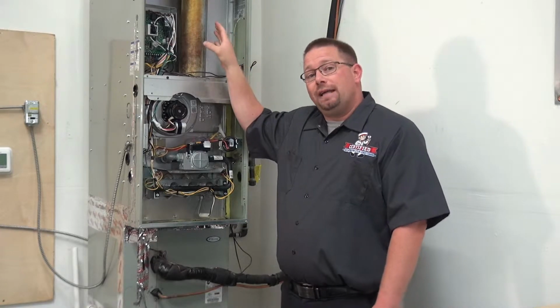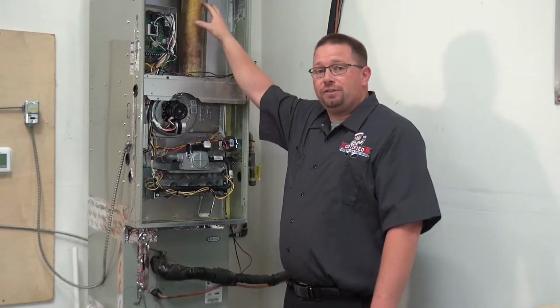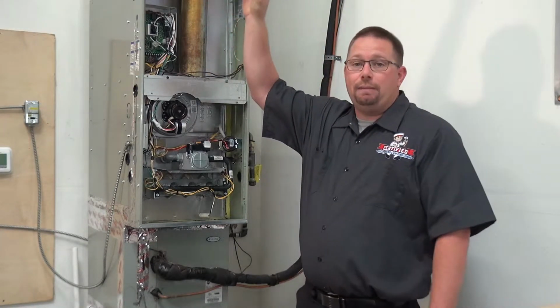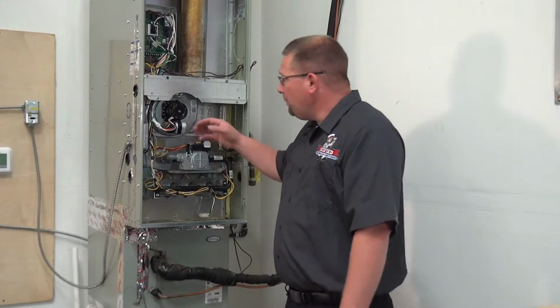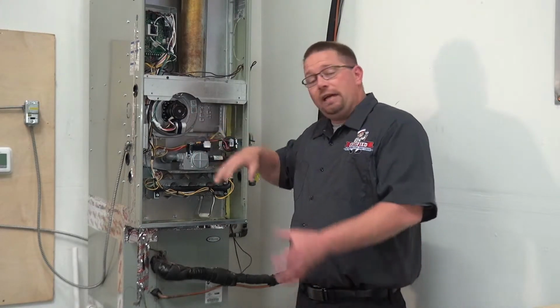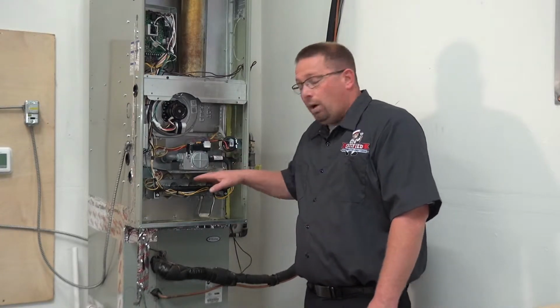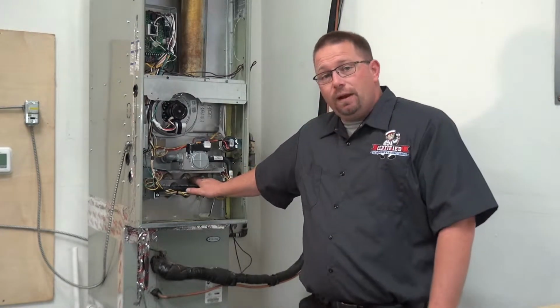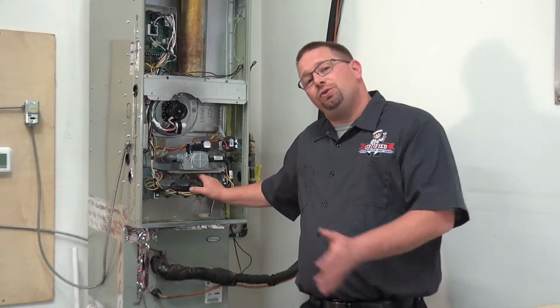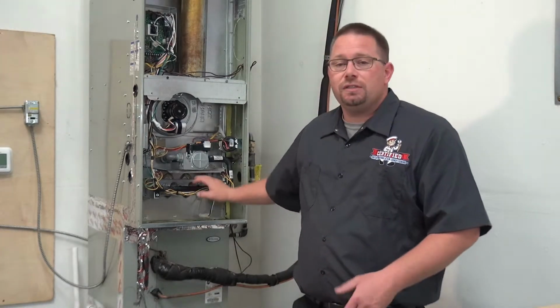So when we go through here to analyze everything, we're going to take this flue riser apart before it gets to the main pipe that goes outside, and look inside to make sure there's no obstructions. We're going to make sure there's no white ash in there, and that it's not rusting from condensation. We're going to pull this inducer motor off and check everything inside, making sure none of the internals are rotted out. We're also going to go through the heat exchanger with an infrared camera inspection to make sure there's no soot, white ash, or rust inside, and no breaches in the heat exchanger.